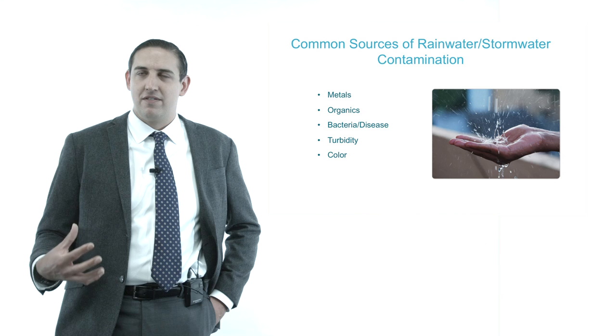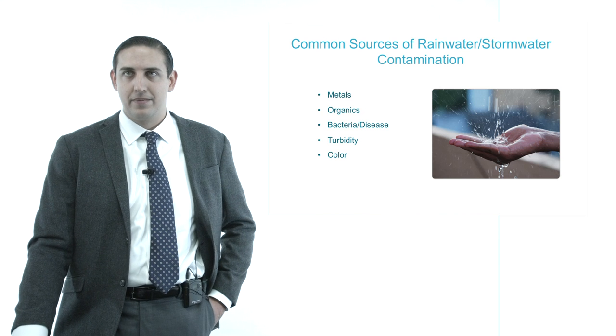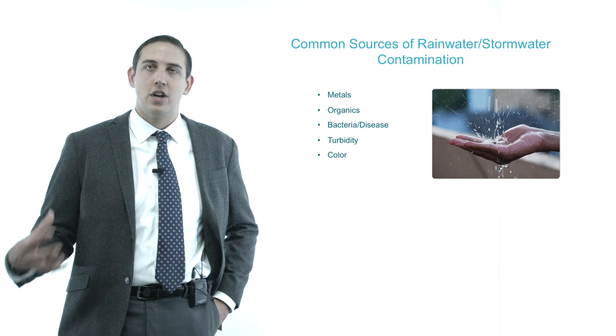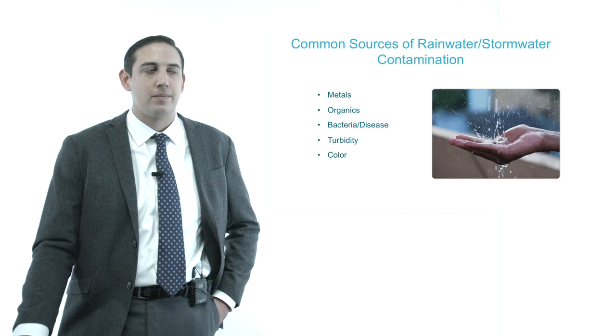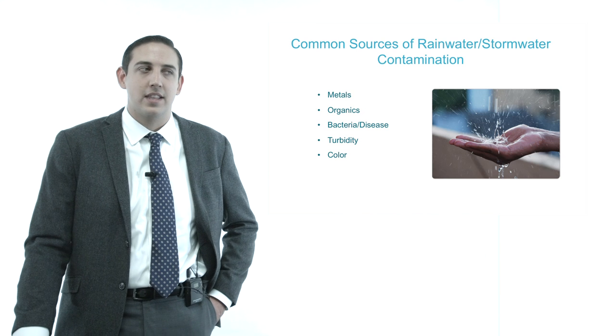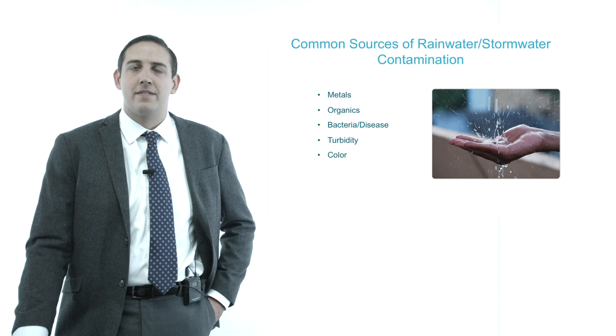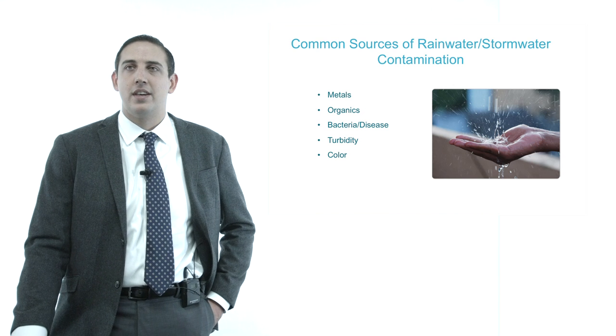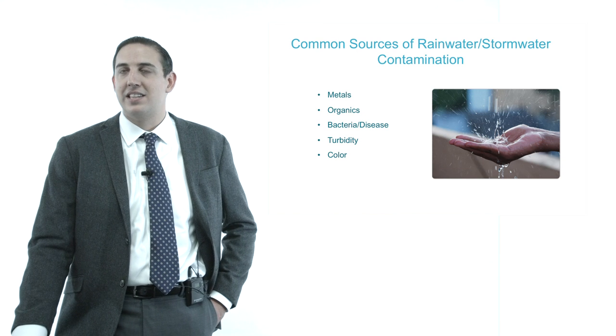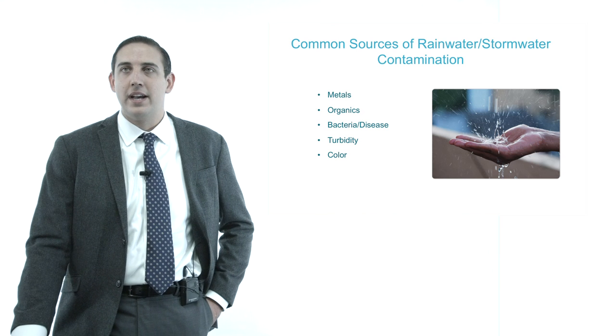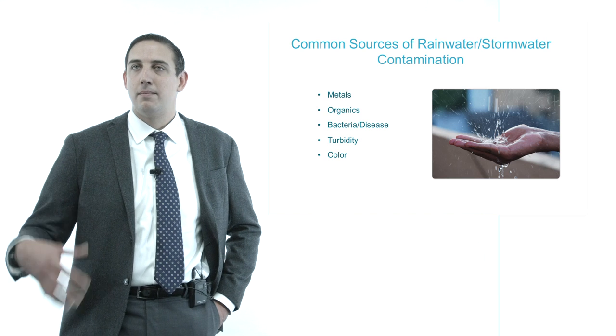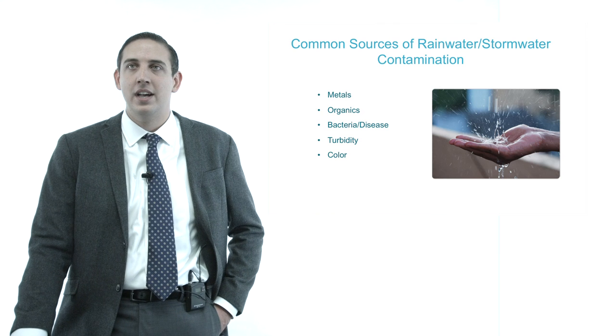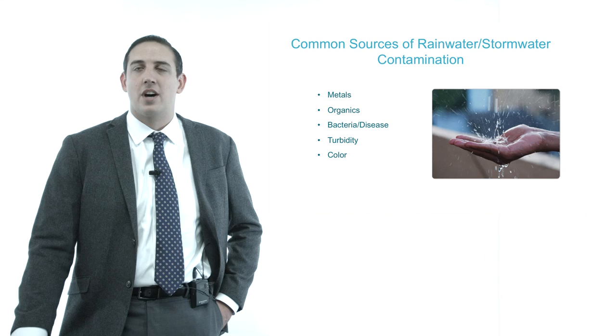The problem is, once rainwater hits the surface and you start collecting it, it is no longer a clean water source. There are five primary sources of contamination found in both rain and stormwater — and stormwater is always more contaminated than rainwater. These are: metals (things like zinc and lead, often from flashing material in roof construction), organics (from fertilizer to smog, which is a particulate that can dissolve into water), bacteria and disease from contact with animals like pigeons or birds, turbidity from particulate matter picked up along the way, and discoloration, often associated with dissolved metals in the water.